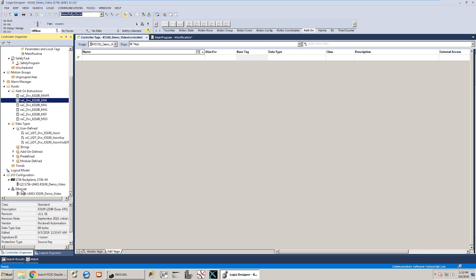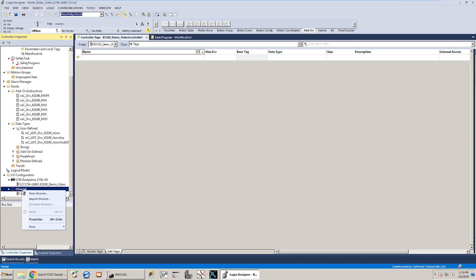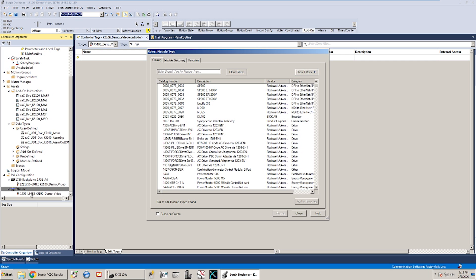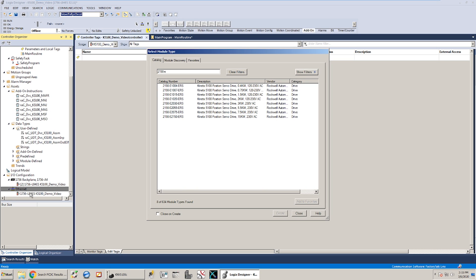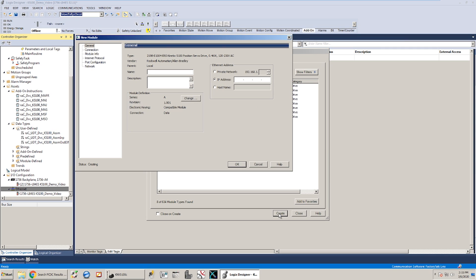So I already loaded that add-on profile that I showed you where to go to download before, but if you haven't loaded that AOP you'll need to do that as well. And once you've done that you can go to your Ethernet network or your Ethernet card or whatever you've got in your IO tree where you're going to be able to add your Ethernet device and search for 2198-E. That's going to show you all the Kinetix 5100 drives. In my case I've got an E1004. I'm going to hit create. I'm going to call this K5100 drives. And again the IP address I had set in for the 5100 tool is .65.